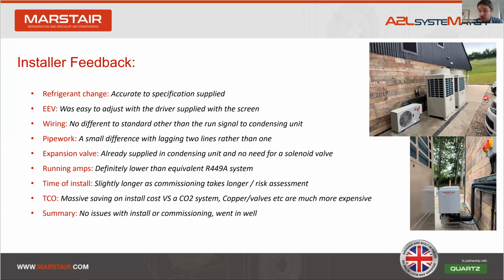Pipe work was very similar. Obviously, you needed to insulate both the suction and the expansion line, which is a little bit different, but it was still very easy to do. The expansion valve already being supplied within the condensing unit, and the fact there's no need for a solenoid valve, made the install a little bit easier. Running amps were clearly lower than equivalent R449A systems he'd installed in the past, which is great from an energy efficiency point of view. You can see that immediately.